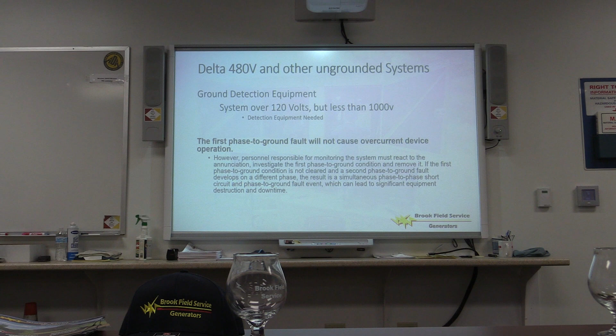Marking equipment, making sure that it's marked for 480 volts, is fairly common. It does give you a notification of the system. The issue that we came across, next slide please, is that in one case they had a motor that kept shorting out, and they couldn't figure it out because the breaker never popped. The breaker wasn't rated for straight 480. And there is the possibility, if you go phase to phase, that your equipment is going to be energized, meaning if you touch it, you're going to get electrocuted. So we brought an engineer in both cases to review what's going on.